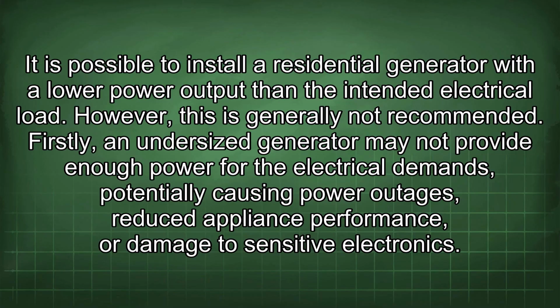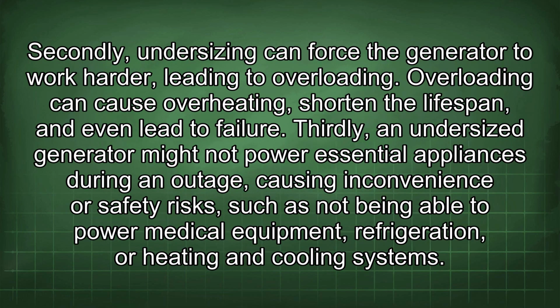It is possible to install a residential generator with a lower power output than the intended electrical load. However, this is generally not recommended. Firstly, an undersized generator may not provide enough power for the electrical demands, potentially causing power outages, reduced appliance performance, or damage to sensitive electronics. Secondly, undersizing can force the generator to work harder, leading to overloading. Overloading can cause overheating, shorten the lifespan, and even lead to failure.